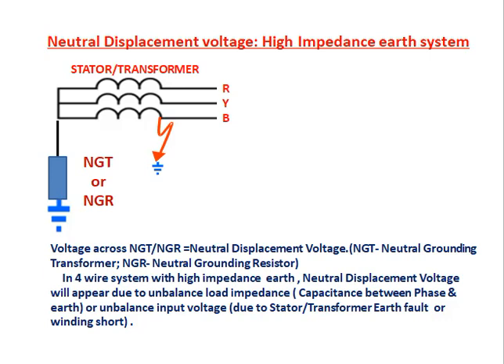Neutral displacement voltage in a high impedance earth system: to control earth fault current, high impedance is connected on the neutral side of the source. One side of the stator winding or transformer is shorted together and connected to earth via high impedance — an NGT (neutral grounding transformer) or NGR (neutral grounding resistor). The voltage across the NGT or NGR equals the neutral displacement voltage. In a 4-wire system with high impedance, neutral displacement appears due to unbalanced load impedance, capacitance between phase and earth, unbalanced input voltage, or stator/transformer earth fault or winding short.